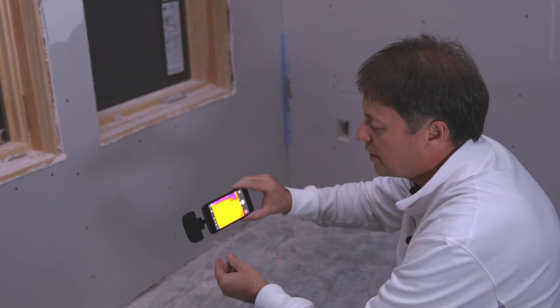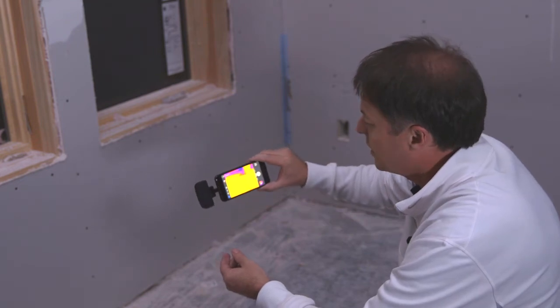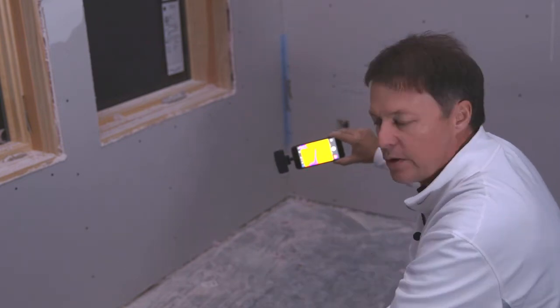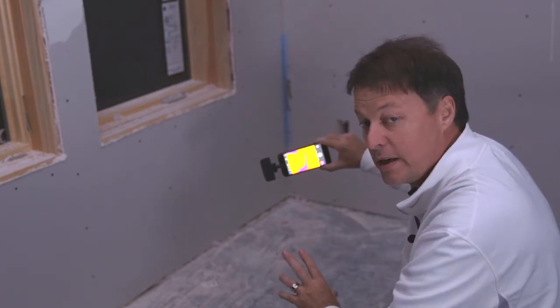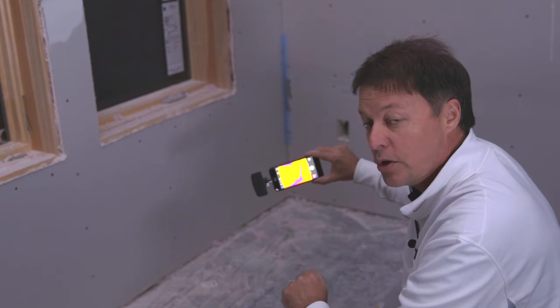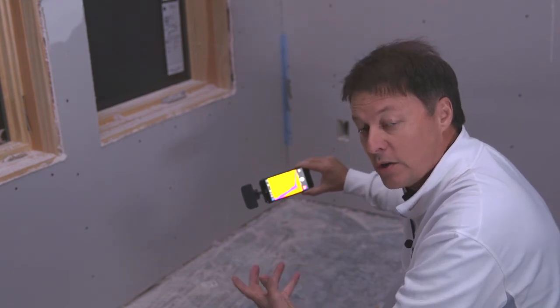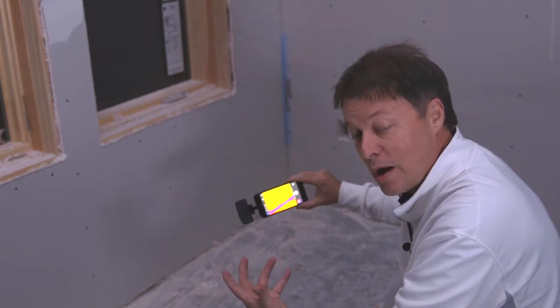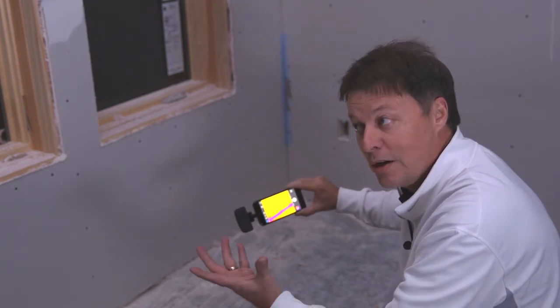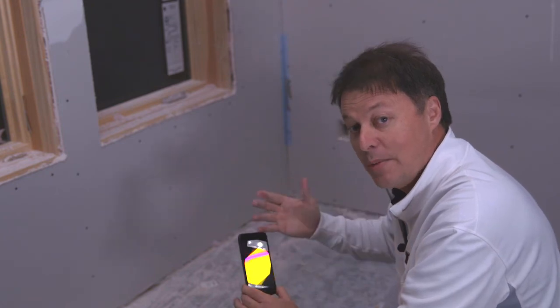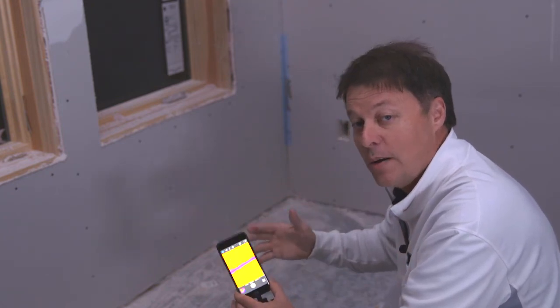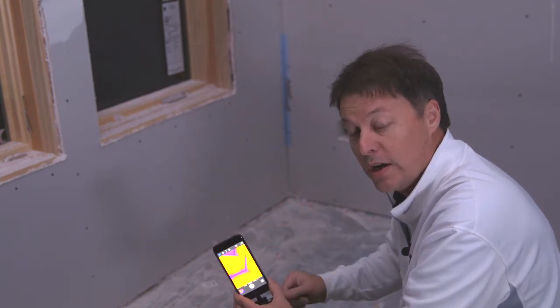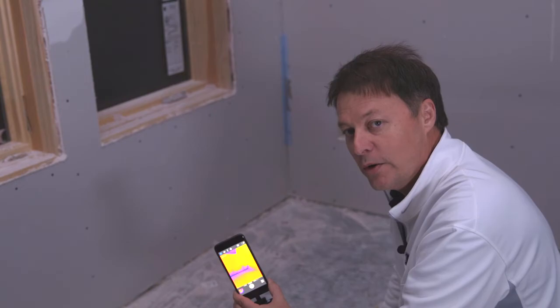As we go through the rest of the wall, you will notice that we really don't have anywhere that we are losing energy except a little bit in the corner, and this is barely any at all. Let me show you where we don't have the front door installed yet and you'll see a big difference. Largely on this house, using this as a training tool, we didn't miss much. The job is actually fantastic. Once we finish everything out, we're going to be under one air change more than likely.